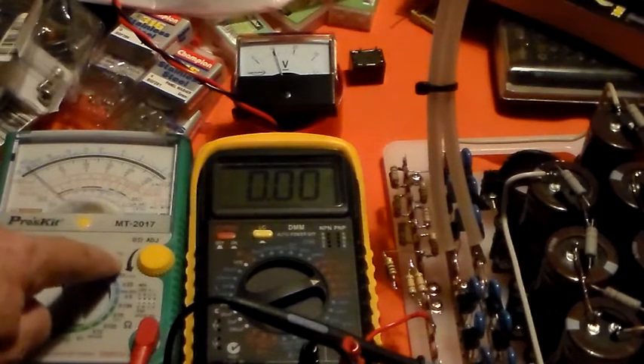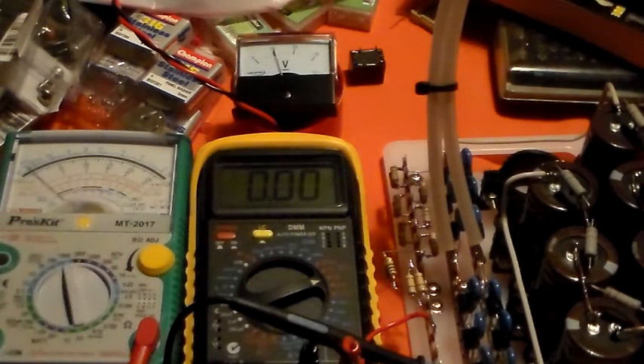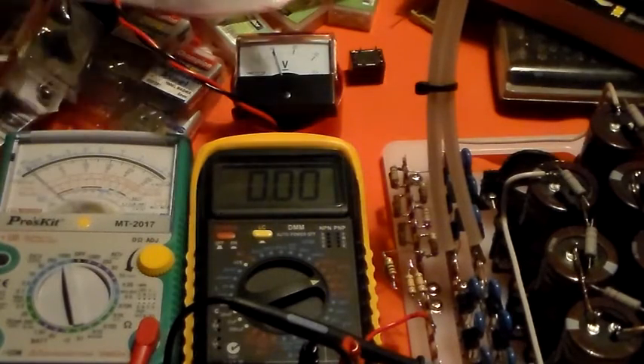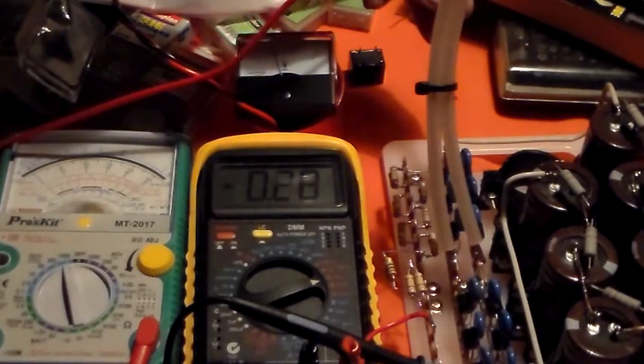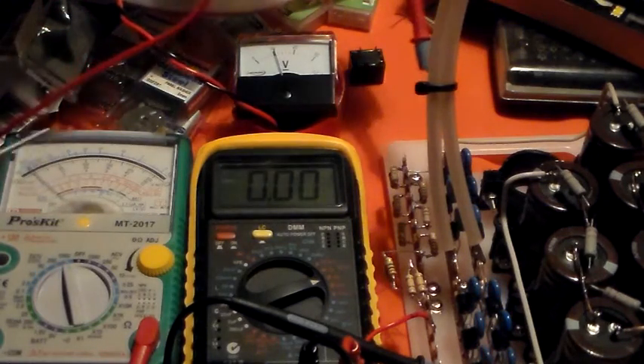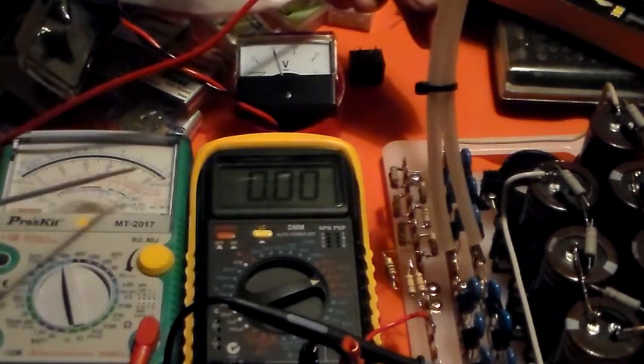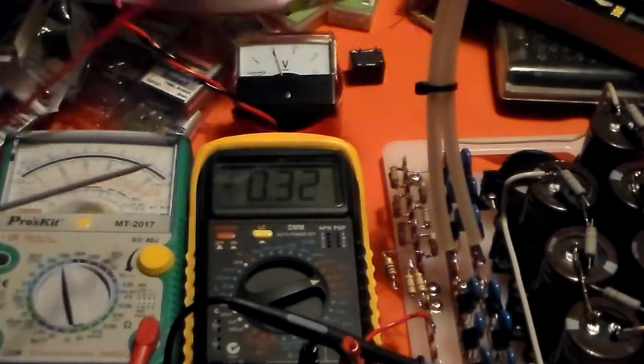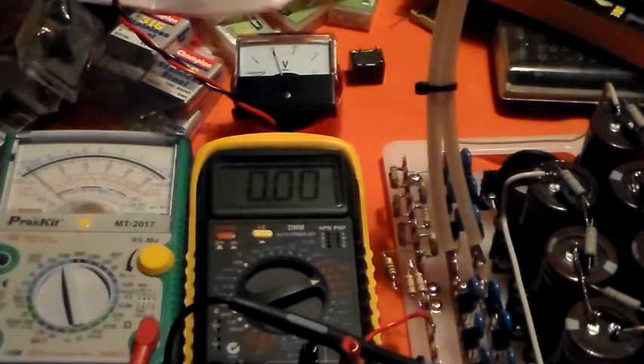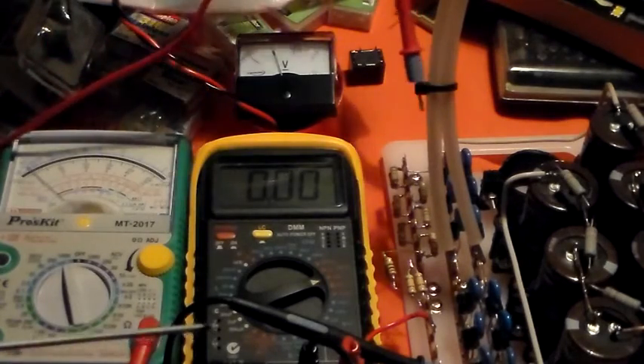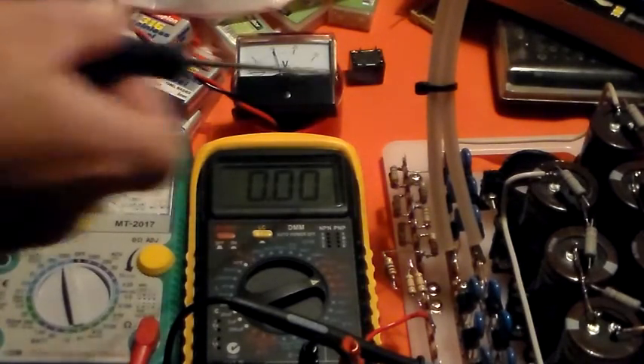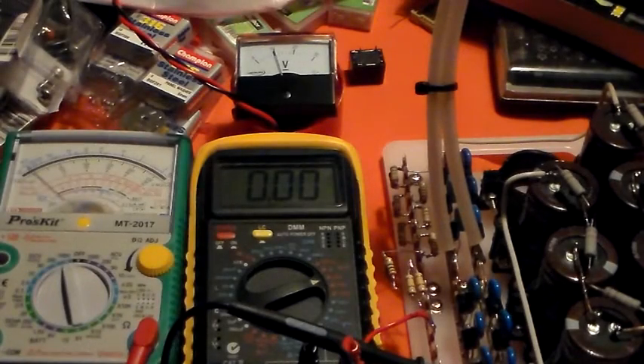Now this meter here has a 1000 volt DC range on it, selected to 1000 volts DC. So if I put a probe on my HT line, you can probably see that's pegging the end there, and because they're connected together here, this isn't grounded. It's picking up a little bit of noise when I put that probe on. Okay, so let's get that going - so you can see 1000 volts there.